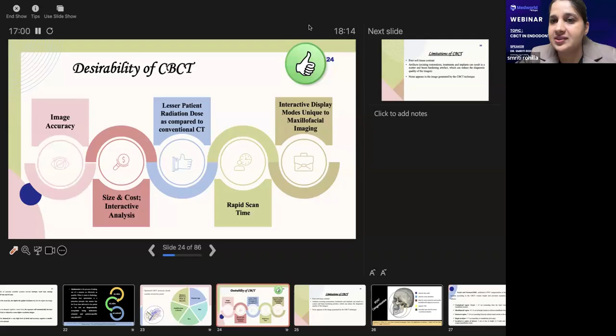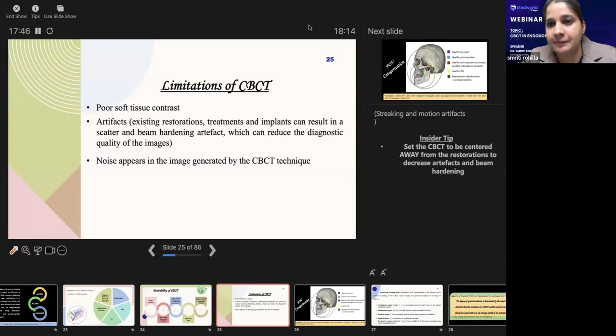Somehow there are certain limitations of CBCT, which include poor soft tissue contrast, or there may be generation of artifacts, which may be due to existing restorations, treatments or implants placed, which actually decrease the diagnostic quality of the images. For these artifacts, there are certain situations where we can ask our diagnostic center to use MAR filters, so that the artifacts are reduced or removed. Another limitation is the noise that appears in the images, generally from the CBCT technique, or because the patient moves in between during the scan. So some kind of artifacts or noise appears during the scan.